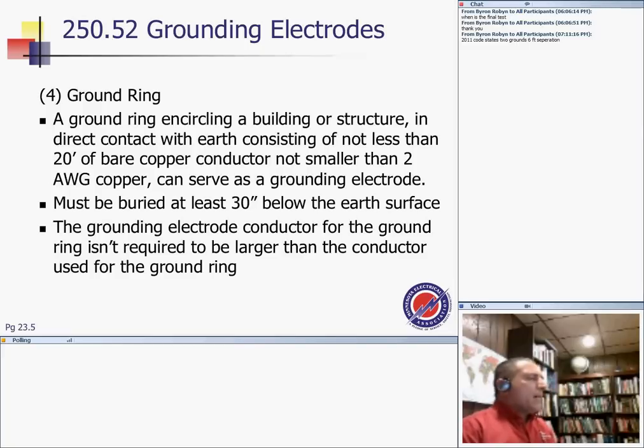The idea, Brenna, is you need to be able to find direct contact with Mother Earth. You can't just throw a wire in the ground and call it a day. There are some restrictions. How do you get direct contact with Mother Earth? As you can see, we have the rebar concrete encased, we have the steel of the building, we have rods. All these are to give us ample connection with Mother Earth. Okay, that's not enough. You can put a ring. With the ring, you need 20 feet of bare copper, of course, not aluminum, and the size is number 2 or larger copper. You can't just put number 6.